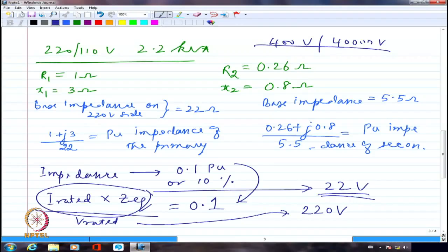One is, just by observing the values, you can say whether the values fall within the normal range for a transformer, for an induction motor, for a synchronous machine. You should be able to say that, because all of us generally who are familiar with electrical apparatus can say transformers should have impedances less than 5%. And similarly, I should be able to say if it is RC or XM, it will be even more than 100%. Maybe 200, 300, 400%. Very high values.